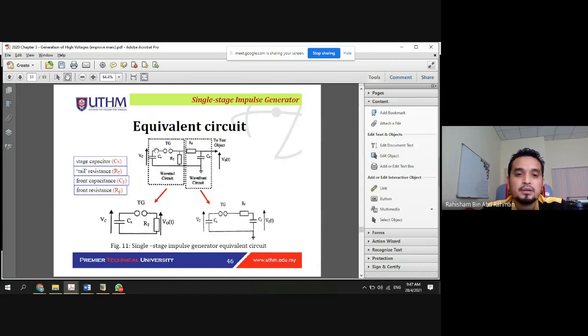This is another important element for the impulse: the trigger gap, TG. Without the trigger gap, we definitely cannot develop or establish the impulse waveform. Why do we need the trigger gap? Once we apply voltage and charge the capacitor to its full level, or maybe half level, the trigger gap is required to short circuit and allow the conduction. We charge this capacitor to a certain value and discharge it by using the trigger gap to short circuit the circuit and allow current conduction.